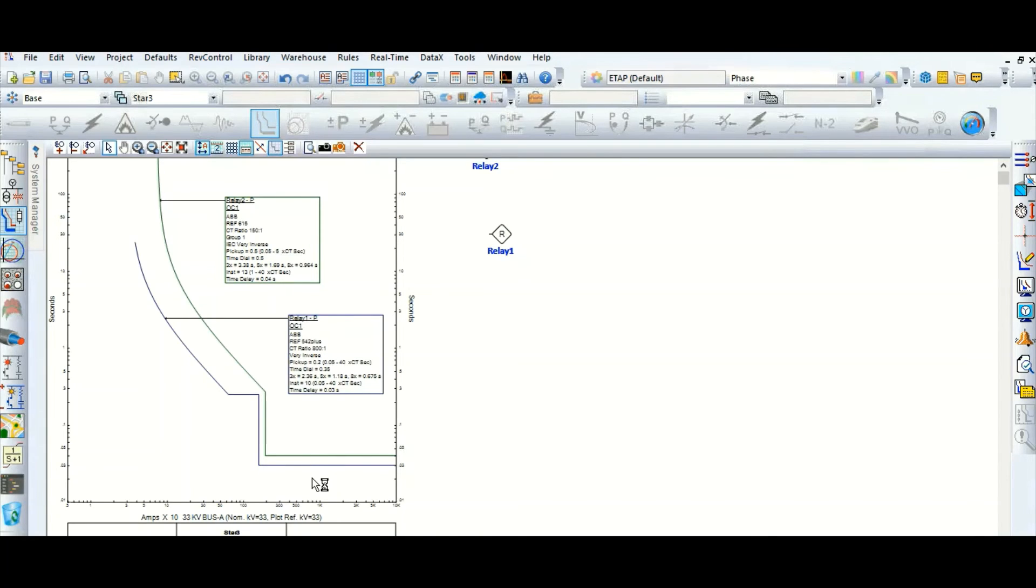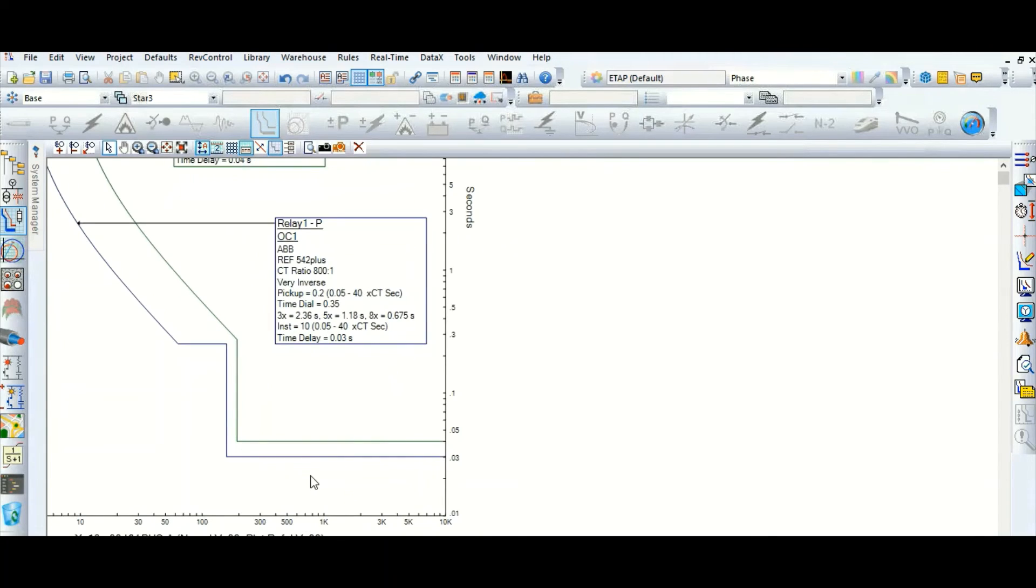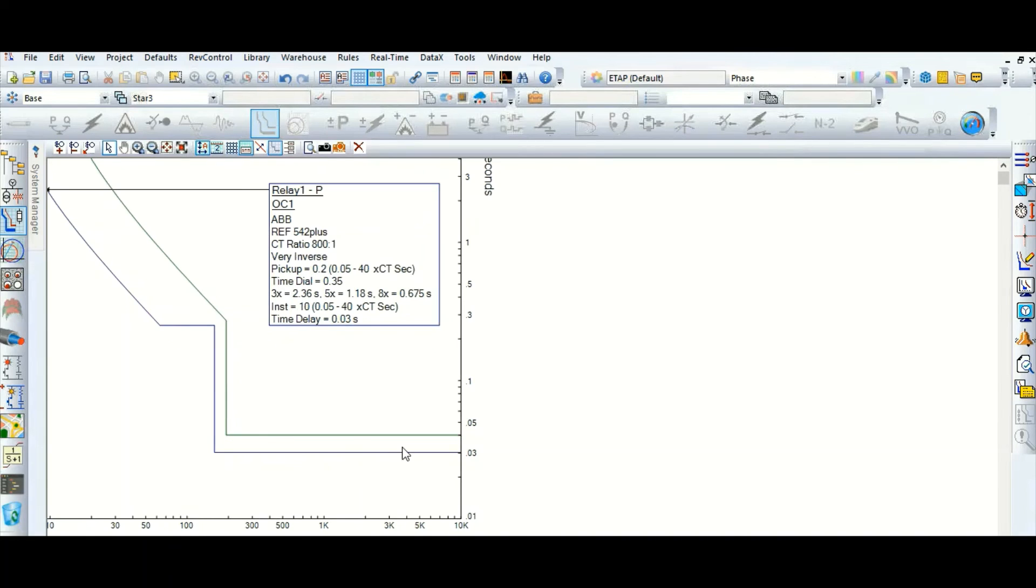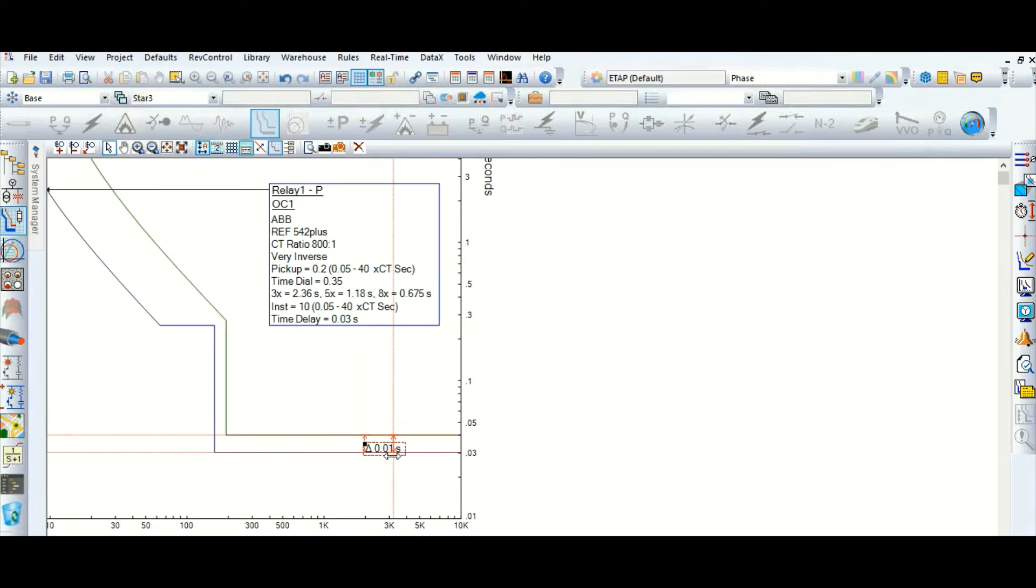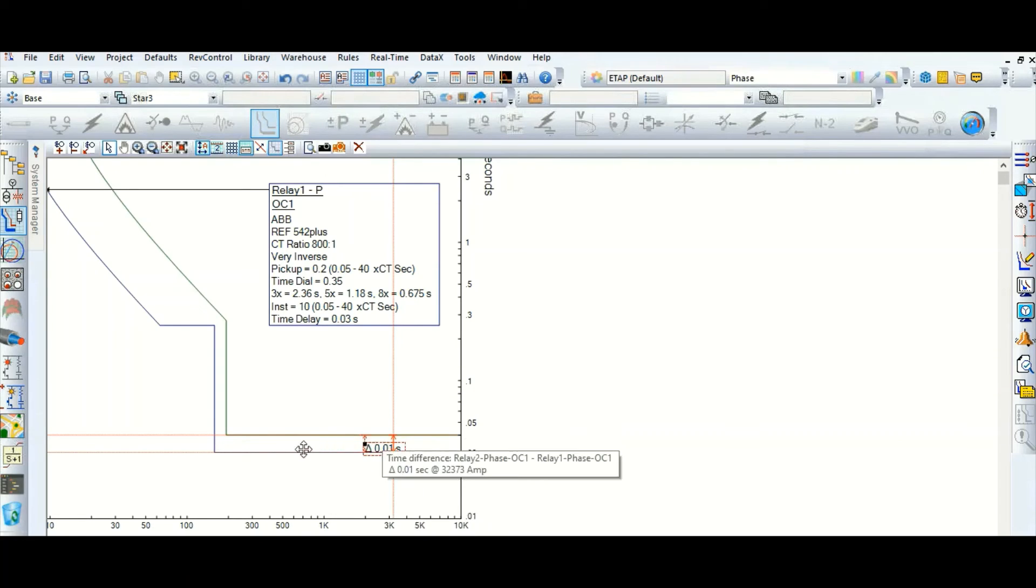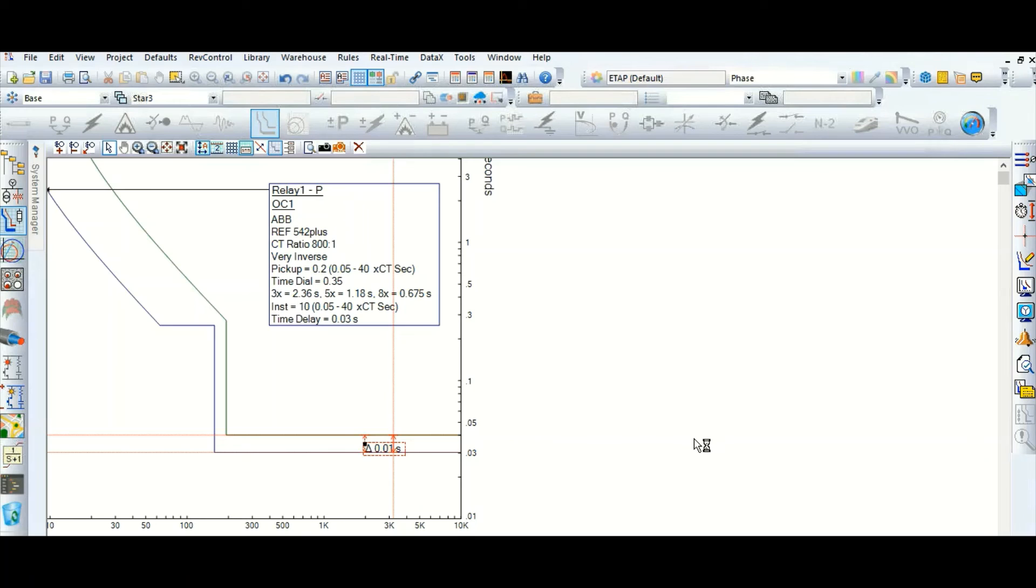This is the coordination, now let's check what's the time gap between these two with the help of this tool. We can check, so only 10 millisecond. That means only 10 millisecond is not sufficient, so we need to coordinate with suitable time discrimination.